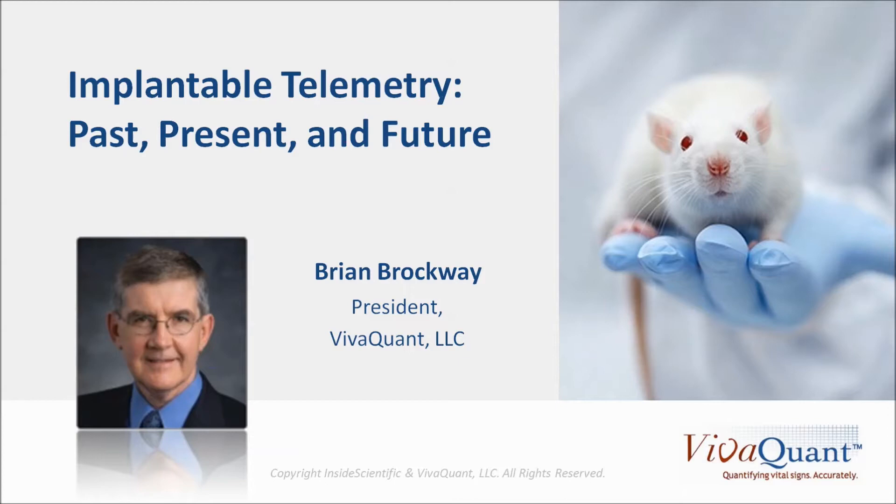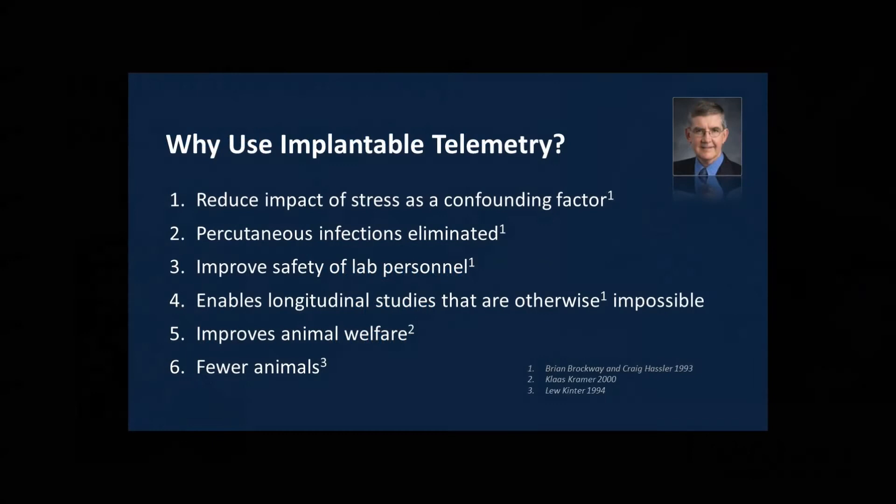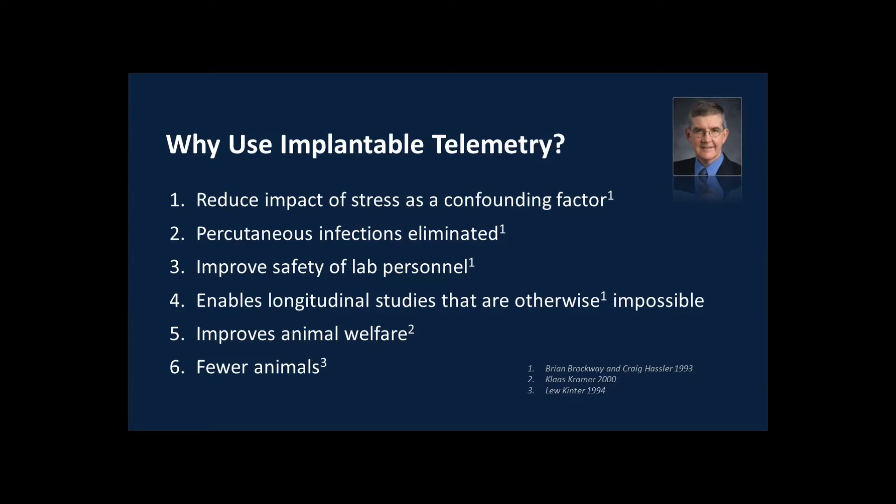His algorithm is unique in that it removes 95% of noise while preserving morphology, resulting in faster, more thorough, and more accurate interval and arrhythmia analysis. First of all, it reduces stress as a confounding factor in studies. It eliminates percutaneous infections relative to tethered systems, improves the safety of laboratory personnel, reduces contact with animals, and reduces potential exposure to hazardous substances. It enables longitudinal studies that are otherwise impossible and improves animal welfare. Lew Kinter did a nice paper in 1994 showing that implantable telemetry enables experimental designs that can reduce animal use by up to 90%.